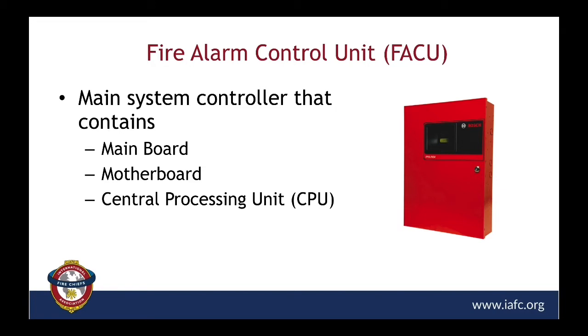Okay, now let's do a little more discussion about the fire alarm control unit. It's really the brains of the system. And the brains of a fire alarm control unit is the central processing unit, or the CPU. Sometimes it's referred to as the motherboard or the main board. This CPU receives signals from the initiating devices or possibly other fire alarm control units or other types of systems. And it processes these signals to determine the required output function, such as activating the alarm notification appliances or triggering other building fire safety control functions, such as HVAC shutdown or elevator recall. Now, all this processing of the input and the output data really happens at very, very high speed.